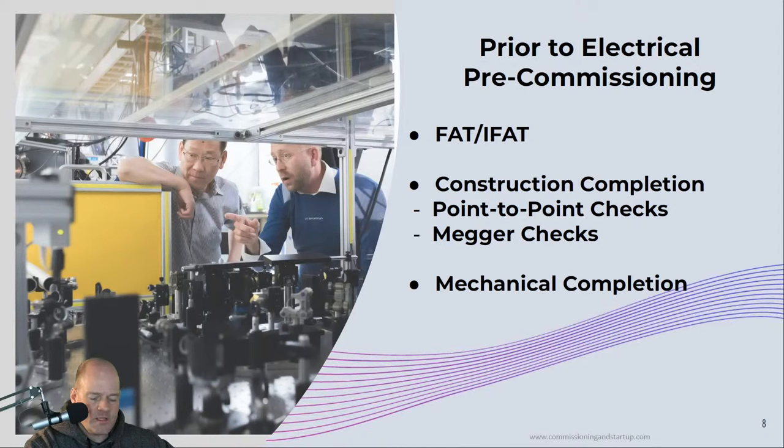Another aspect to focus on is construction completion. Our construction counterparts will be installing and assembling the equipment. There are certain aspects they'll test in their inspection test plans prior to handover to commissioning — things like point-to-point checks to confirm cables are pulled and terminated correctly, and Megger checks to ensure cables aren't damaged. This process is called mechanical completion. Mechanical completion defines the system to be handed over, the level of QA/QC to be completed, and the date when that system is handed over to the commissioning team.